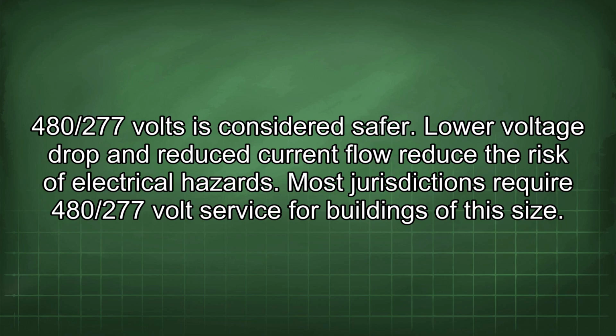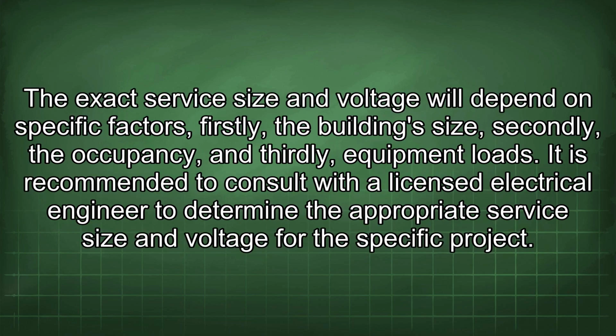480/277 volts is considered safer. Low voltage drop and reduced current flow reduce the risk of electrical hazards. Most jurisdictions require 480/277 volt service for buildings of this size. The exact service size and voltage will depend on specific factors. Firstly, the building size, secondly, the occupancy, and thirdly, equipment loads.